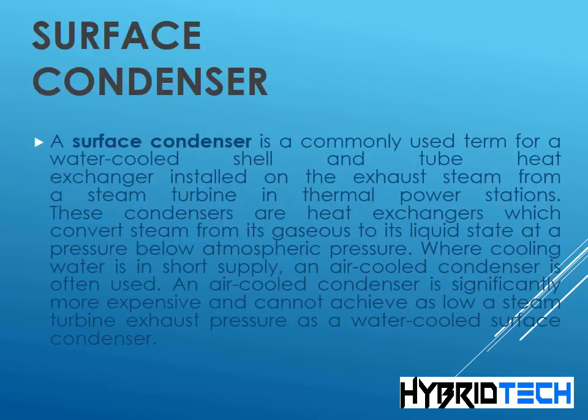Surface condenser: a surface condenser is a commonly used term for a water-cooled shell and tube heat exchanger installed on the exhaust steam from a steam turbine in thermal power stations. These condensers convert steam from its gaseous to its liquid state at a pressure below atmospheric pressure. Where cooling water is in short supply, an air-cooled condenser is often used, though it is significantly more expensive and cannot achieve as low a steam turbine exhaust pressure as a water-cooled surface condenser.